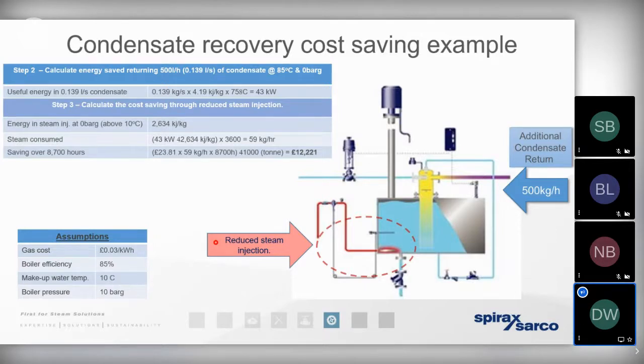by returning as much condensate as we could, compared to using raw water from the mains and then using direct steam injection to top up the temperature. So on this occasion, you can see that we'd be saving approximately 59 kilograms of steam per hour. And that doesn't sound like a great deal, but over the course of a year, that means that we'd be saving just over £12,000 sterling per year, simply by increasing the rate of condensate return by 500 kilograms per hour. But that's scalable. So if we doubled the amount of condensate we can recover, well, the cost savings would double as well.